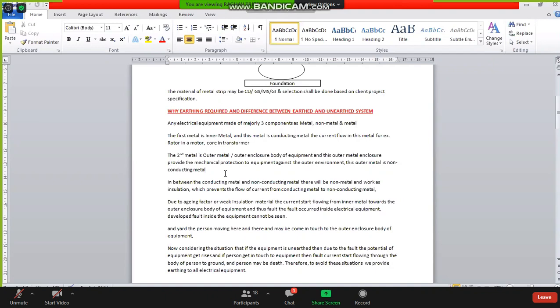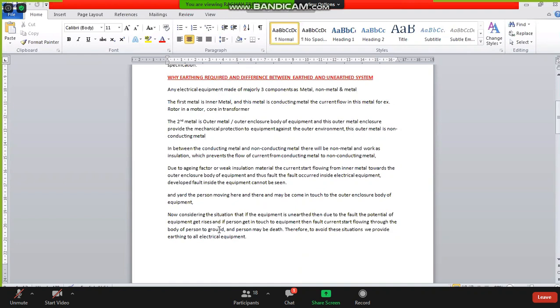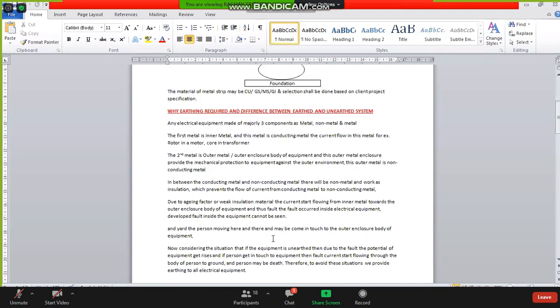Due to aging or weak insulation material, current starts flowing from the inner metal or conductors towards the outer enclosure body of the equipment, and thus a fault occurs inside the electrical equipment. A fault developed inside the equipment cannot be seen from outside. In the yard, a person moving here and there may come in touch with the outer enclosure body of the faulty equipment. If the equipment is unearthed, then due to the fault the potential of the equipment rises, and if a person touches it, fault current starts flowing through the person's body to the ground, and the person may die. Therefore, to avoid these situations, we provide earthing to all electrical equipment.